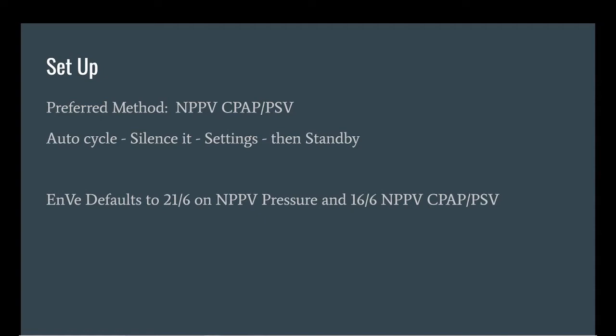because it can't sense a patient. It can't sense any pressure resistance. And so it thinks it's just detached. So it'll try 4 or 5 times, then it will just stop attempting breaths altogether. So hit the silence button, type in your settings, then click on standby. That way your settings match the hospital's and they're ready for you when you hit start resume. It'll start pushing out air and you can push the mask onto your patient. The EnVe does default at 21/6 for the NPPV pressure mode, and it does default at 16/6 for NPPV CPAP PSV.